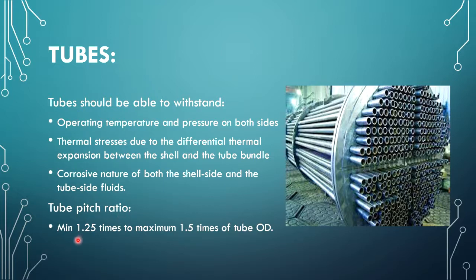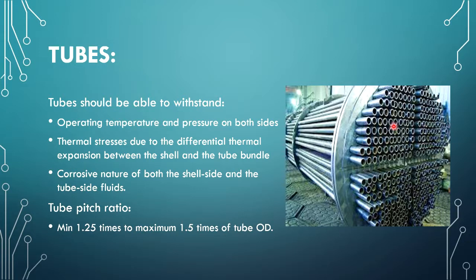The tube pitch ratio is normally between 1.25 to 1.5 times the outside diameter of the tube. One fluid passes inside the tubes and another fluid passes outside the tubes, and heat transfer takes place between them.